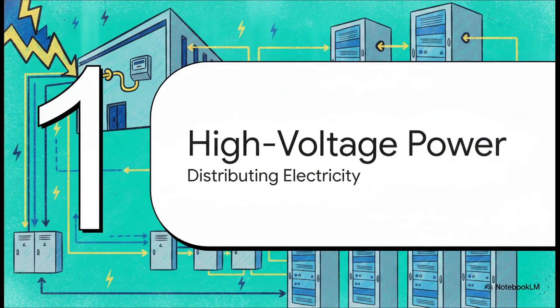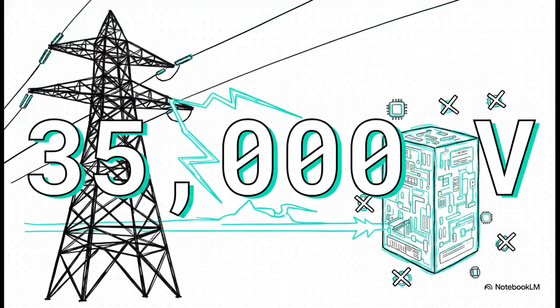Let's jump into concept number one: distributing high voltage power. Taking a macro to micro approach, we start at the moment electricity arrives from the utility grid, coming in at a massive scale, often between 13,000 and 35,000 volts. Data centers have an enormous, constant power demand, and that raw influx of power is enough to literally vaporize sensitive electronics. It's way too much voltage for a server to handle directly.